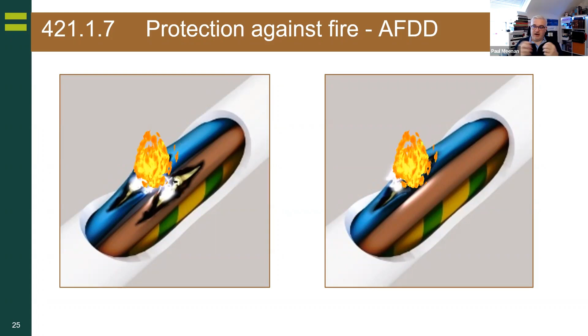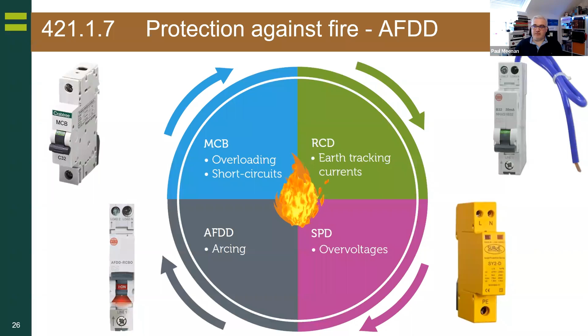Now, there's some great visuals for learning these, because anyone of whatever age you're learning of, MCBs are your base principle: fuses, MCBs, that's for overloads and short circuits. Your RCD is your earth leakage, or earth tracking as they say in Europe. We then have, in the recent editions, surge protection and AFDDs. I personally think surge protection is a given, and we'll cover that in a second. With AFDD, I adopt a rule of thumb of what's the utilization of the installation. Be very careful. This is, to me, an additional protection measure. Who is using this? This is a care home, and we'll get onto that in a second.